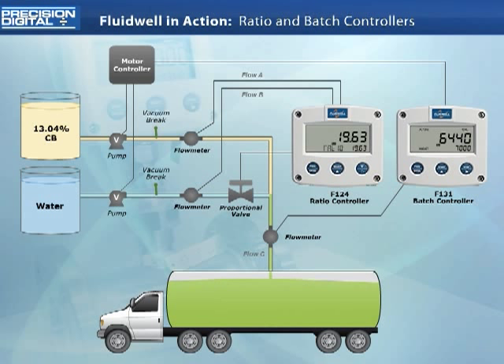This activates the vacuum breaks, and the fluid remaining in the system, already past the pumps, can drain into the truck. As the last flow drains into the truck, the full 7,000 gallons has been accurately dispensed. The batch controller knows from past batches that an overrun was expected and automatically calculated the overrun cutoff time, turning off the relays just early enough that this excess flow would be counted in the batch process.